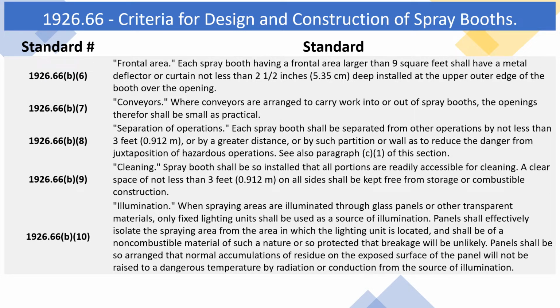1926.66(b)(8) Separation of operations. Each spray booth shall be separated from other operations by not less than 3 feet (0.912 meters), or by a greater distance, or by such partition or wall as to reduce the danger from juxtaposition of hazardous operations. See also paragraph (c)(1) of this section. 1926.66(b)(9) Cleaning. Spray booths shall be so installed that all portions are readily accessible for cleaning. A clear space of not less than 3 feet (0.912 meters) on all sides shall be kept free from storage or combustible construction.